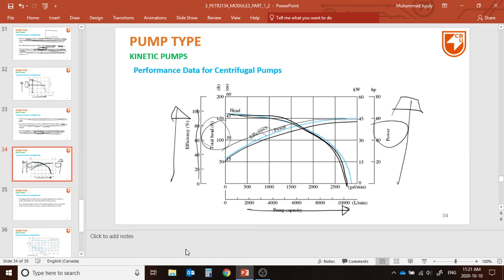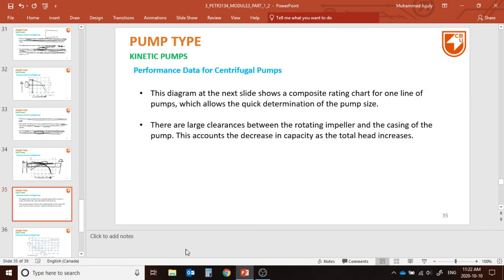All right, so based on that, you remember the 60 to 80% range of the efficiency belt. In this range, you see that there's a cut set. That means finding an optimum point, what the pump should be. It's not that at this point you will find the pump is the most desirable type, but mostly it's based on this area, the sweet spot, but it totally depends on the type of operation you actually need.